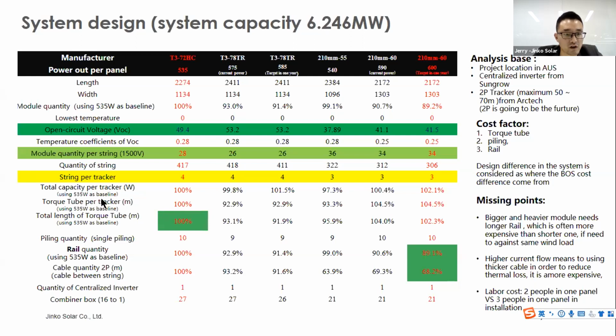But if we look at the torque tube length per tracker and the total length of torque tube, you'll find that the advantages and disadvantages will be reversed. So for same capacities, 210 modules will use more torque tube than the 182 solar modules. If the 210 solar module power is less than 600 watts, let's say 590, these advantages will be greater.